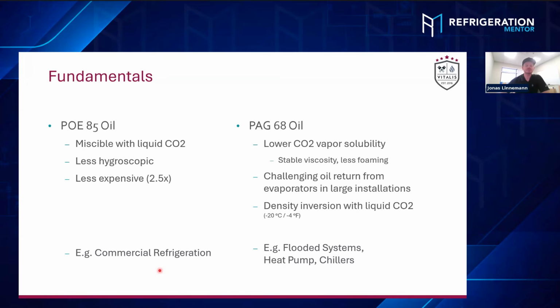POE 85 viscosity is not as stable as PAG 68. So when we say POE 85, as the temperature starts to rise, for an example in the discharge, our viscosity starts to change a lot more than 68. Is that correct? Yeah, the main factor for that is not actually the temperature. The temperature definitely impacts the viscosity, but it's the dissolved CO2 vapor, because the amount of dissolved CO2 vapor compared to the pressure changes the viscosity a lot. CO2 is not a good lubricant, so the more CO2 you dissolve, the less good the oil is lubricating. So that's the main factor here.